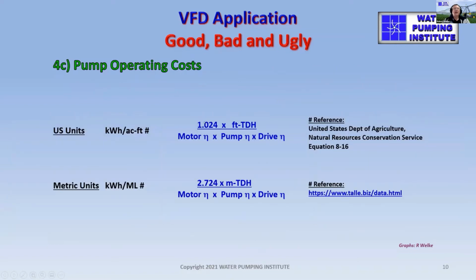One of the things we look at is how to calculate the cost of power, and we do that in terms of kilowatt hours per acre feet. And here's the formula in US units: 1.024 times feet head, total dynamic head, divide by motor efficiency times pump efficiency times drive efficiency, and that's taken from the NRCS book. There are 3 very important components of this that we're interested in. In using a VFD, one of the main aims might be to reduce the total dynamic head, and the other, we need to look at the pump efficiency, and we need to also take into account the drive efficiency. So there are three areas that we look at that will determine largely how a VFD will perform and how much savings it will derive for us.